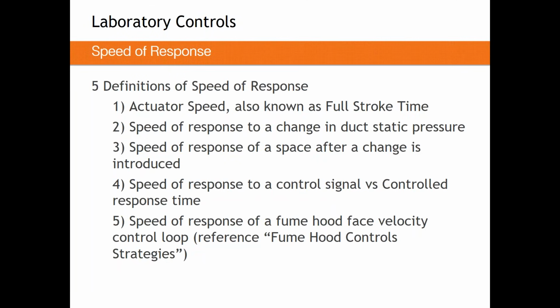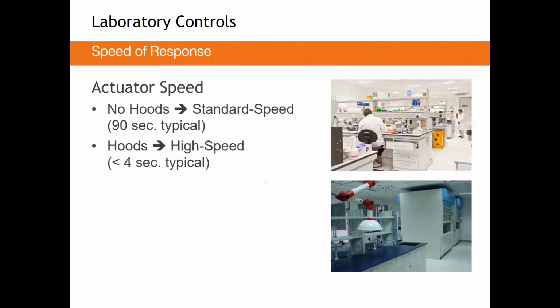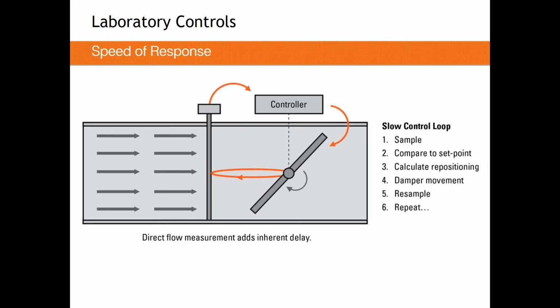The next type is speed of response to a control signal, or we might call this controlled response time. So if you look at a closed loop style of device, it needs to sample the airstream, compare that sample to the set point, calculate where it would like to go, go there, and then resample and repeat. This can happen at a very, very high speed, but it still takes time. No matter how fast processors and controllers get, this will still take some time.